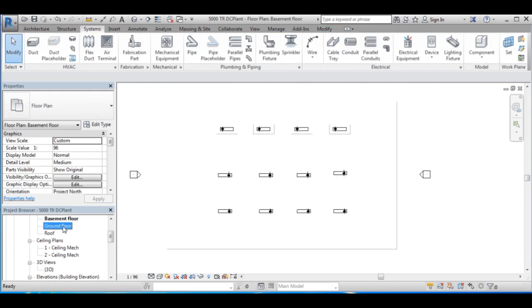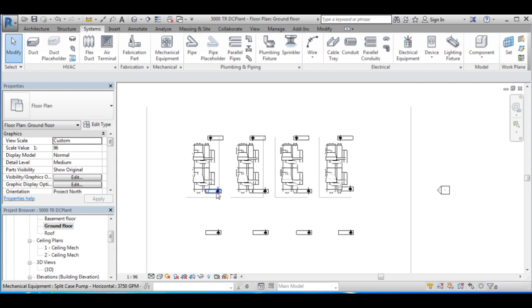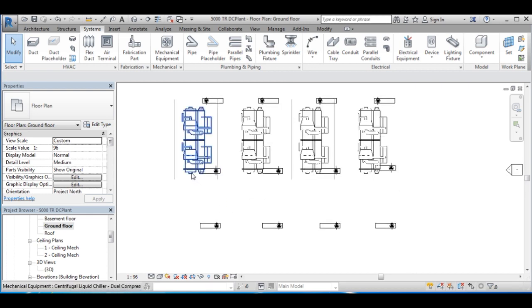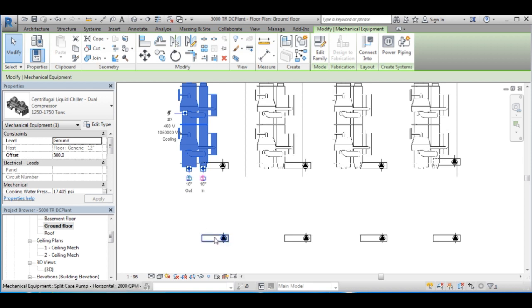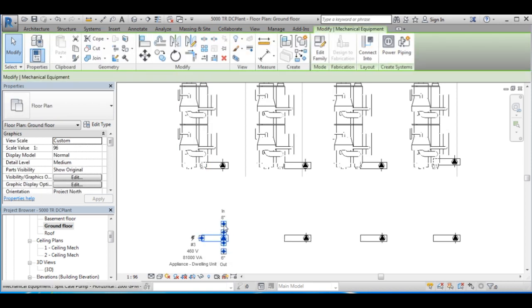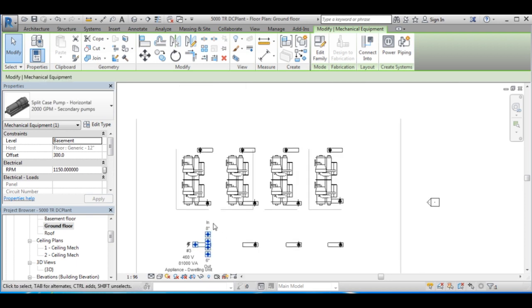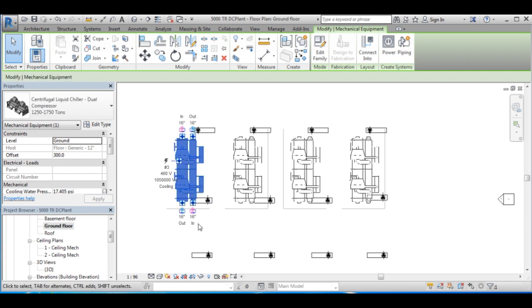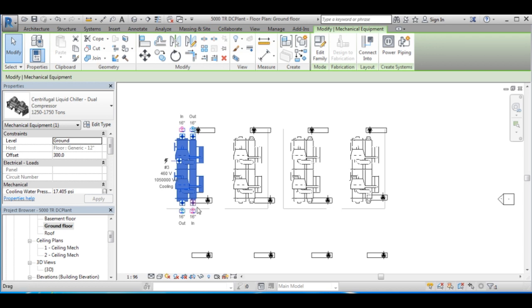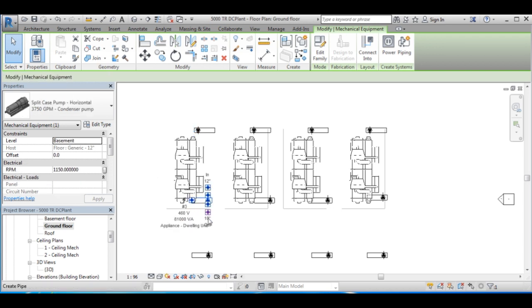After I placed the condenser pumps, I will go again to ground floor and adjust the orientation and location if necessary. The chilled water supply from the chiller is from this side, so the suction of my secondary pump should be from this side. Condenser water inlet to chiller is from this side, so the discharge of condenser pumps should be from this side. My pump positions and orientation are okay, so I will go back to basement to place the foundations.